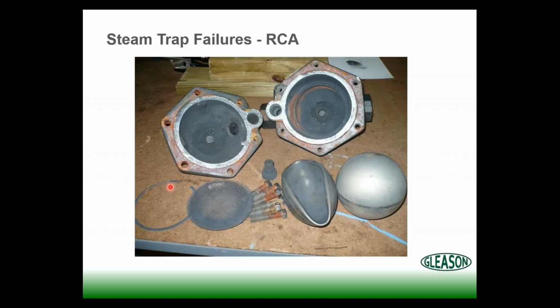Also, let me encourage you, if you have any steam traps that fail, please do a root cause analysis of failure and figure out why it failed. We have this particular steam trap in our shop, and here's what the ball in this particular style of trap, a floating thermostatic, should look like. Here's what it looks like. If we put a new ball in or replace the trap with one just like it, what's going to happen to it? The same thing. So let's figure out why it failed and address the problem. This is a water hammer problem here.